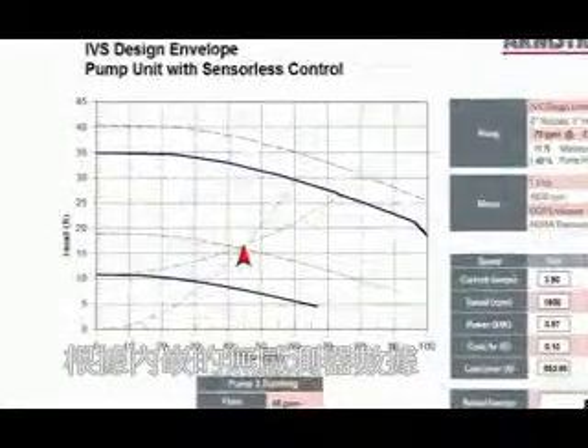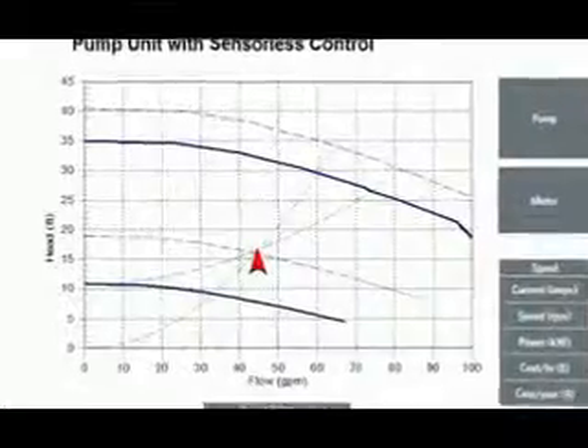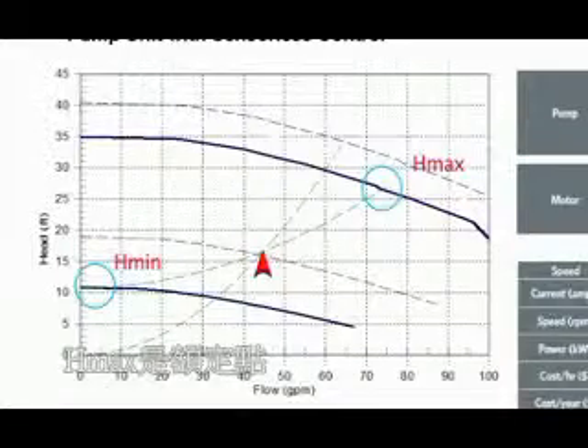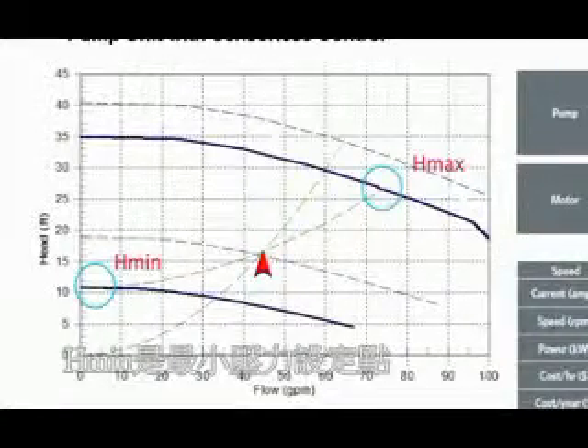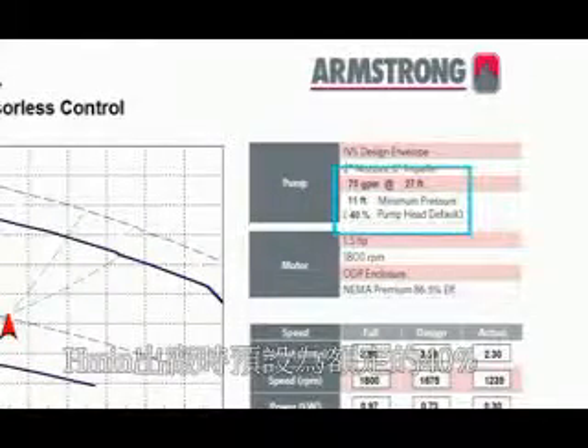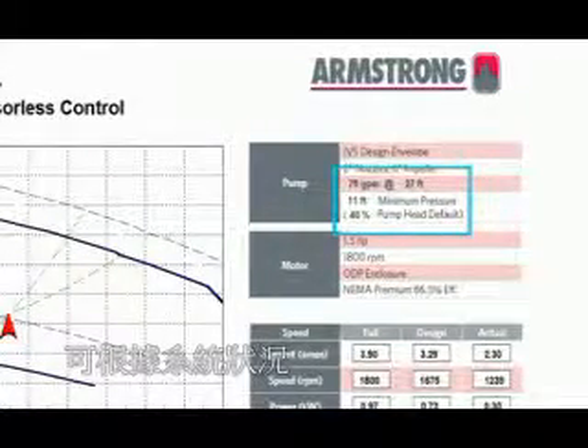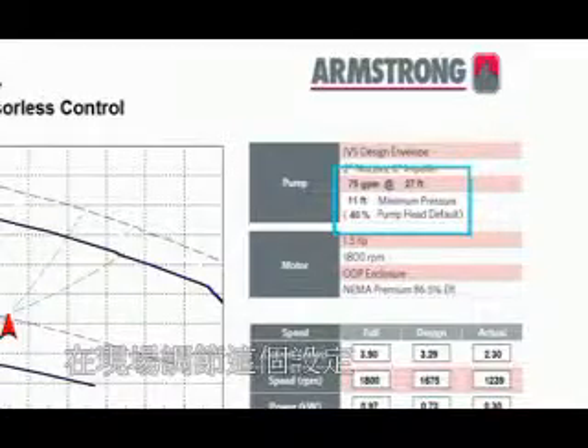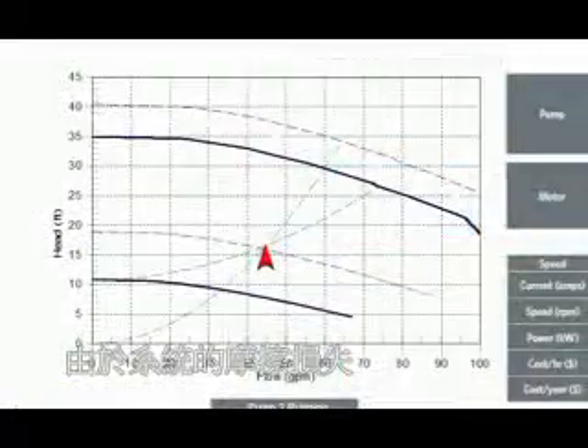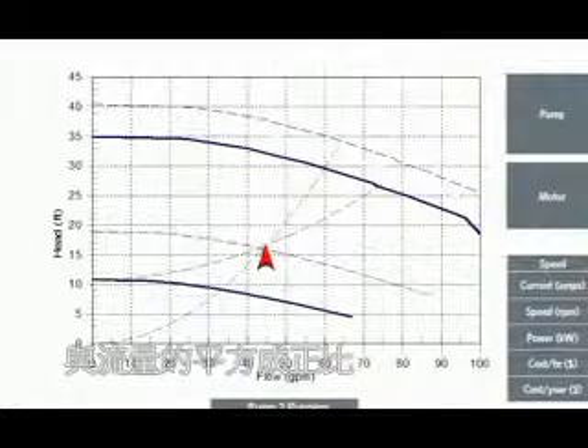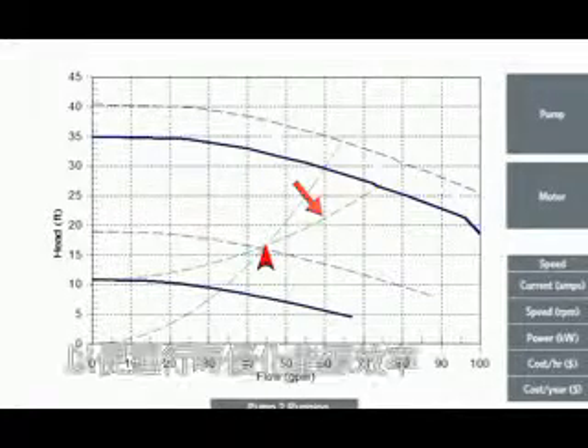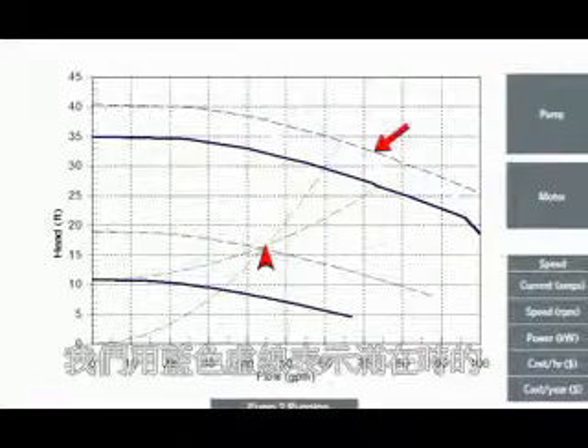Here you can see the pump performance curve, one pump operation. From the embedded sensorless data, the pump's control curve is mapped between two reference points, Hmax and Hmin. Hmax is the duty set point while Hmin is the minimum pressure setting. This is factory set at 40% of the duty point. This value can be easily changed on site to suit specific system performance. Since a system's friction losses have a quadratic relationship to flow, the sensorless control curve adopts a quadratic form for optimum energy-efficient operation. We have our full capacity design envelope speed curve shown in the dotted blue line.